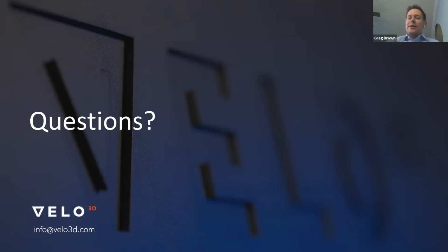That's an interesting question, and basically the printer has a lot of those capabilities built into it. For instance, in the low angle skin defect detection, we're getting thermal emission data from the melt pool itself. The system is designed so that it can run in closed loop control, where it can modulate the laser parameters to try to control that signal.